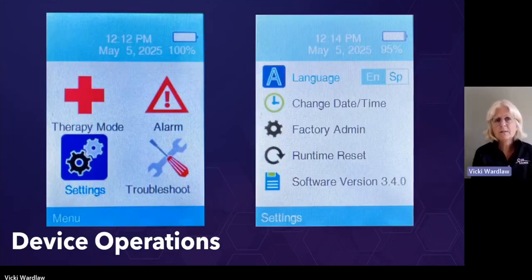Troubleshooting, I told you a little bit about what that is. It's basically instructions that automatically come up. If you want to read it, you would go in there and they're all there. Settings, the blue gear, that's where you can go in and change your language from English to Spanish. You can change your date and time. You can also zero out that runtime that's on the home screen, the hours and the minutes. If you want to zero that out with your dressing changes to make your math easier, you can do so there.